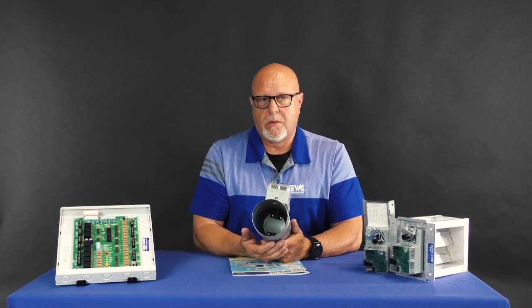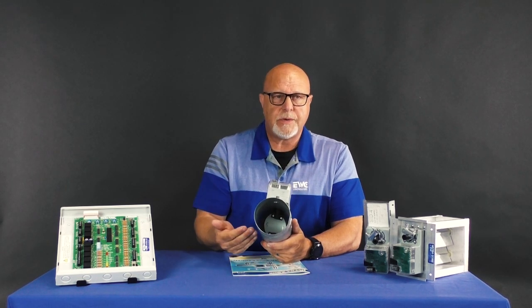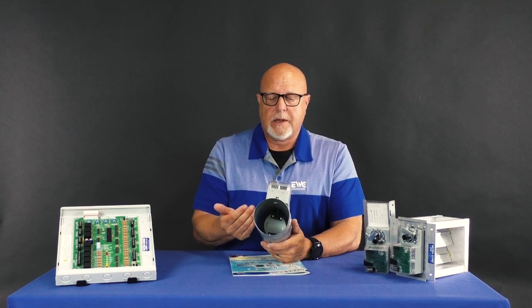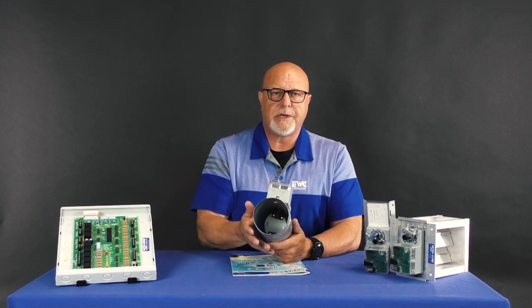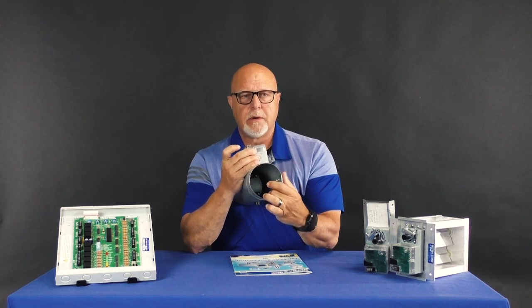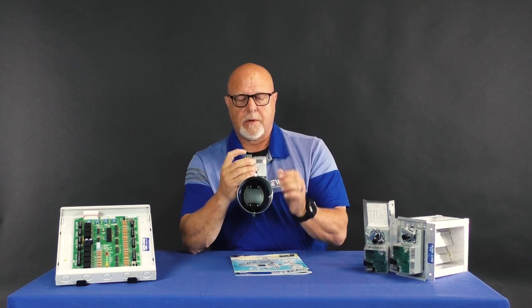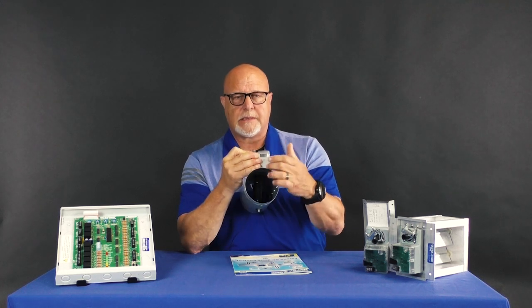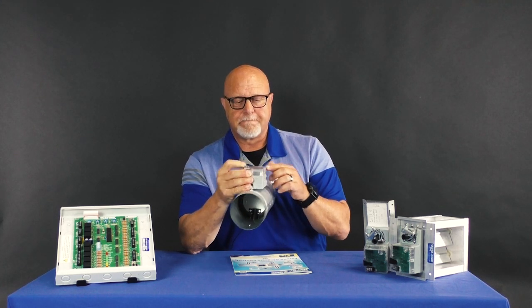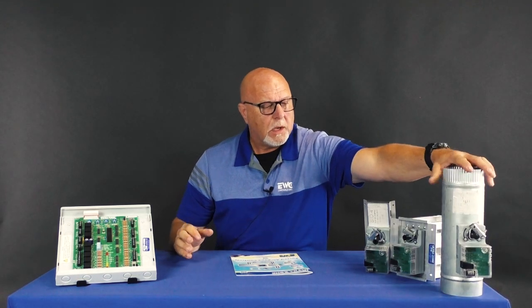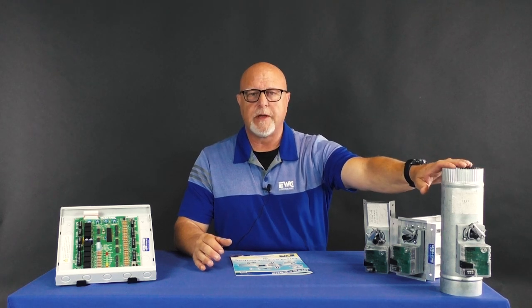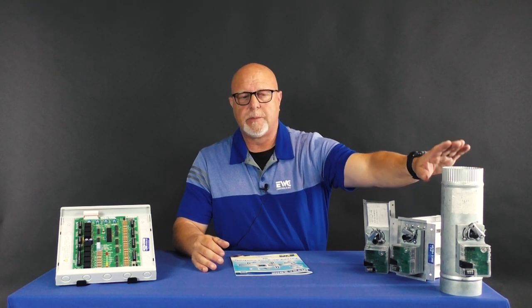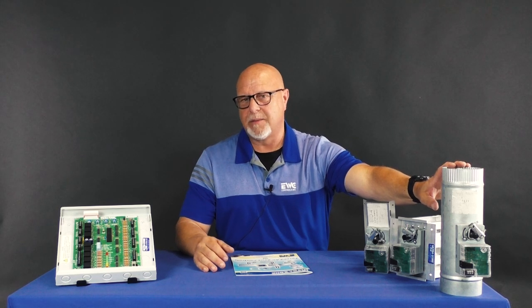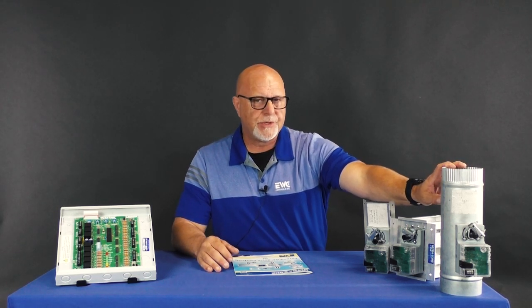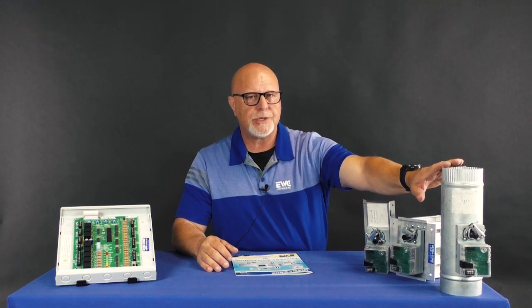The answer is no. Now you are having to increase your velocity to compensate for this restriction in here. I give you the full diameter of this damper except for the shaft, but everyone has the shaft, okay? Moving along, I should point out that this damper is available 4 through 20 inch. Most of my competition stops at 18, some of them even 16. Most of my competition do not offer a 4 or 5 inch, which we do have available.